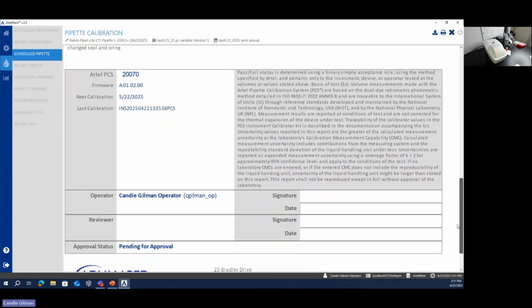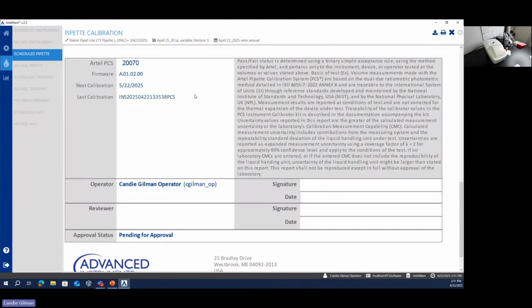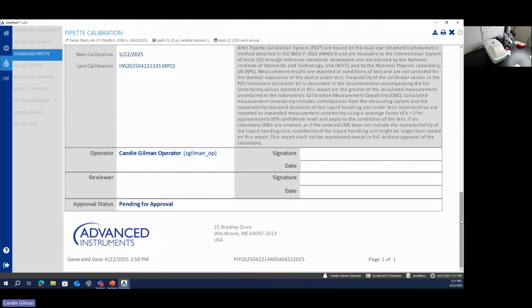And then if I continue to scroll, you'll see information about the PCS system when it's next due for calibration. And in this particular case, I don't have the compliance suite electronic signatures enabled. So you do see operator information here, but the signature boxes are blank because, again, I don't have the e-signatures enabled. But then down bottom, you see the Advanced Instruments logo, the address, etc.